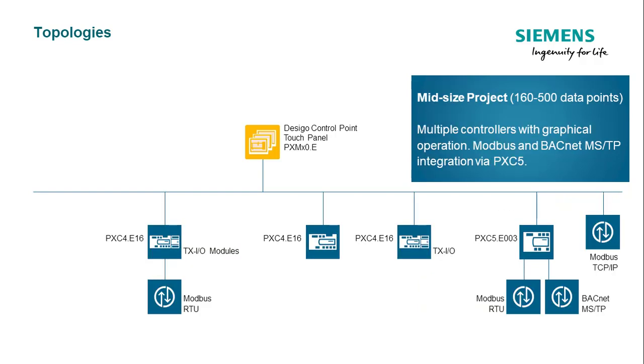For a relatively bigger system, it is also possible to have a mix of BACnet IP and MSTP topology. The system controller PXC5 can integrate BACnet MSTP and Modbus simultaneously, leading to a cost-effective solution. The monitoring and operating of this extended system can also be handled by a Desigo control point with embedded web server.